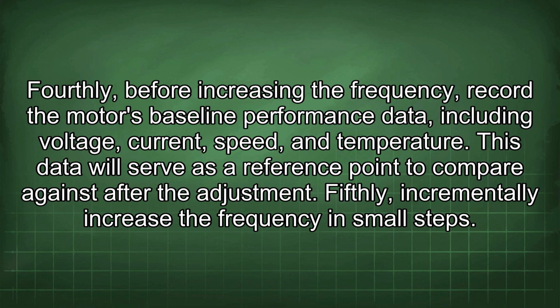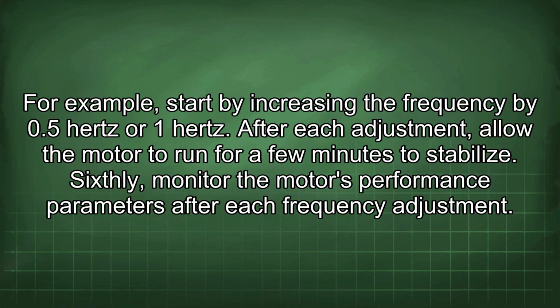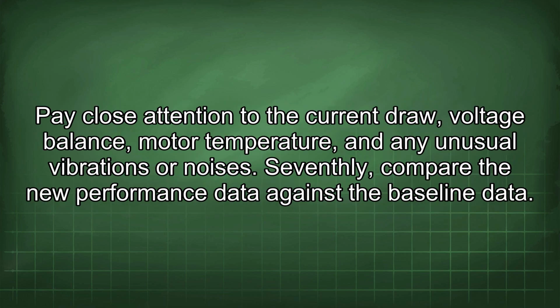Fifthly, incrementally increase the frequency in small steps. For example, start by increasing the frequency by 0.5 Hz or 1 Hz. After each adjustment, allow the motor to run for a few minutes to stabilize. Sixthly, monitor the motor's performance parameters after each frequency adjustment. Pay close attention to the current draw, voltage balance, motor temperature, and any unusual vibrations or noises.